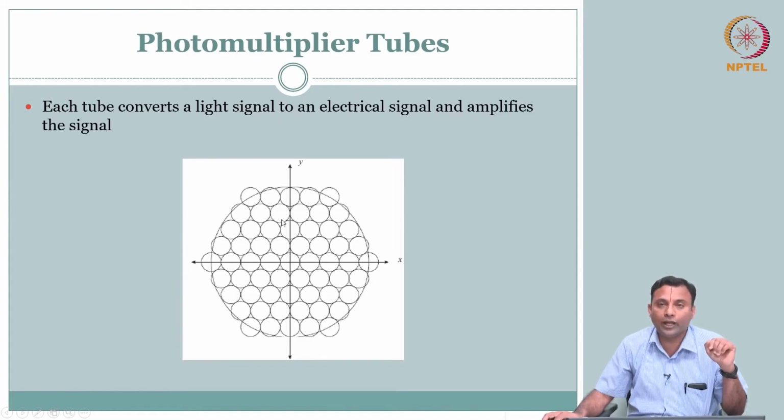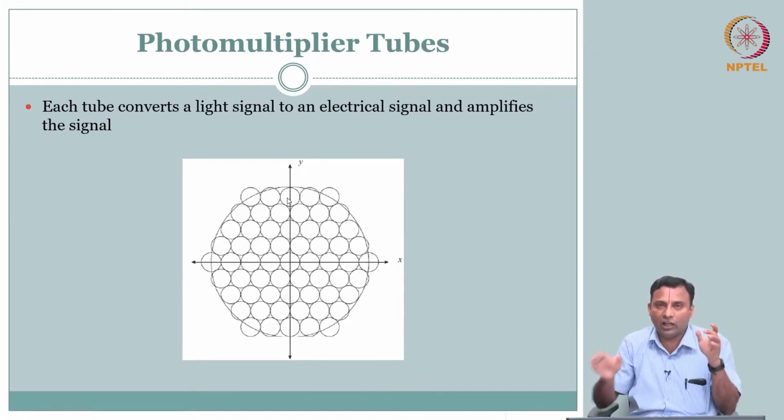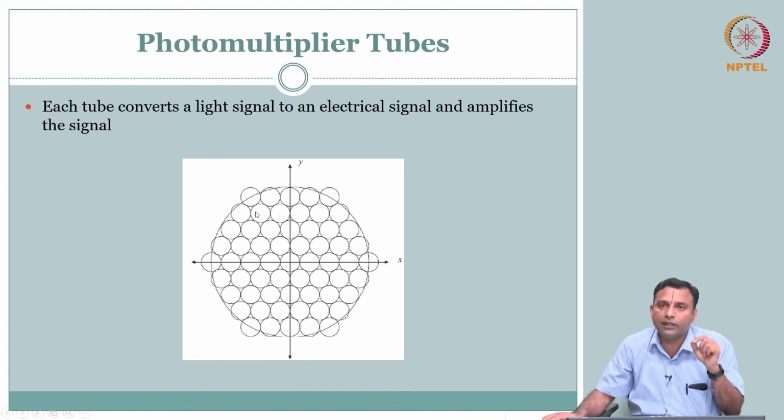So depending on the location where the light comes out, more of it will enter the nearest photomultiplier tube. The photons going to the side can enter the others as well, but the majority will enter along the line of sight, along the collimator and crystal. The objective of the photomultiplier tube is to convert these light photons into an electrical quantity. So now we will see what this photomultiplier tube is.